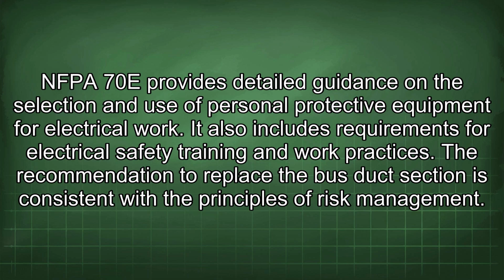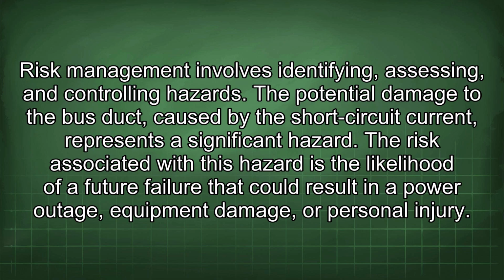The recommendation to replace the bus duct section is consistent with the principles of risk management. Risk management involves identifying, assessing, and controlling hazards. The potential damage to the bus duct caused by the short-circuit current represents a significant hazard. The risk associated with this hazard is the likelihood of a future failure that could result in a power outage, equipment damage, or personal injury.